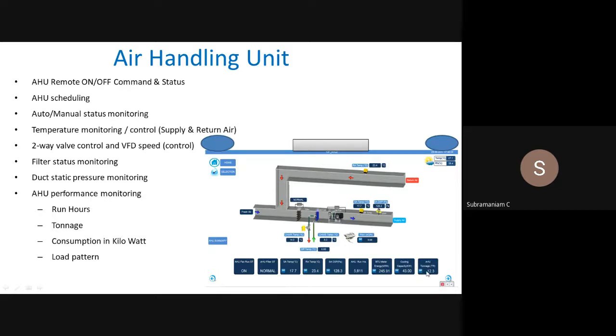What is my AHU tonnage? Where is it coming from? There is a BTU meter put on the chilled water line, so from there itself I can get the tonnage. Then what is my BTU energy value, my AHU run hours, static pressure, return air temperature, supply air temperature, AHU fan run status. All these values we can get for monitoring purposes.